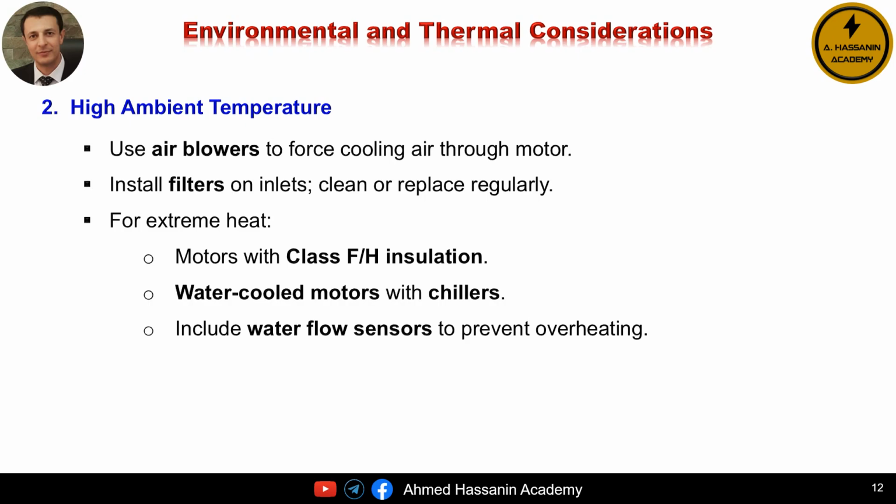These water-cooled motors need water flow sensors. If the cooling water stops flowing for any reason, the sensor triggers an alarm and can even cut the motor power automatically to prevent overheating. So, the takeaway, in hot environments, make sure your motors are properly cooled, whether by air or water, and always monitor the system to prevent overheating.